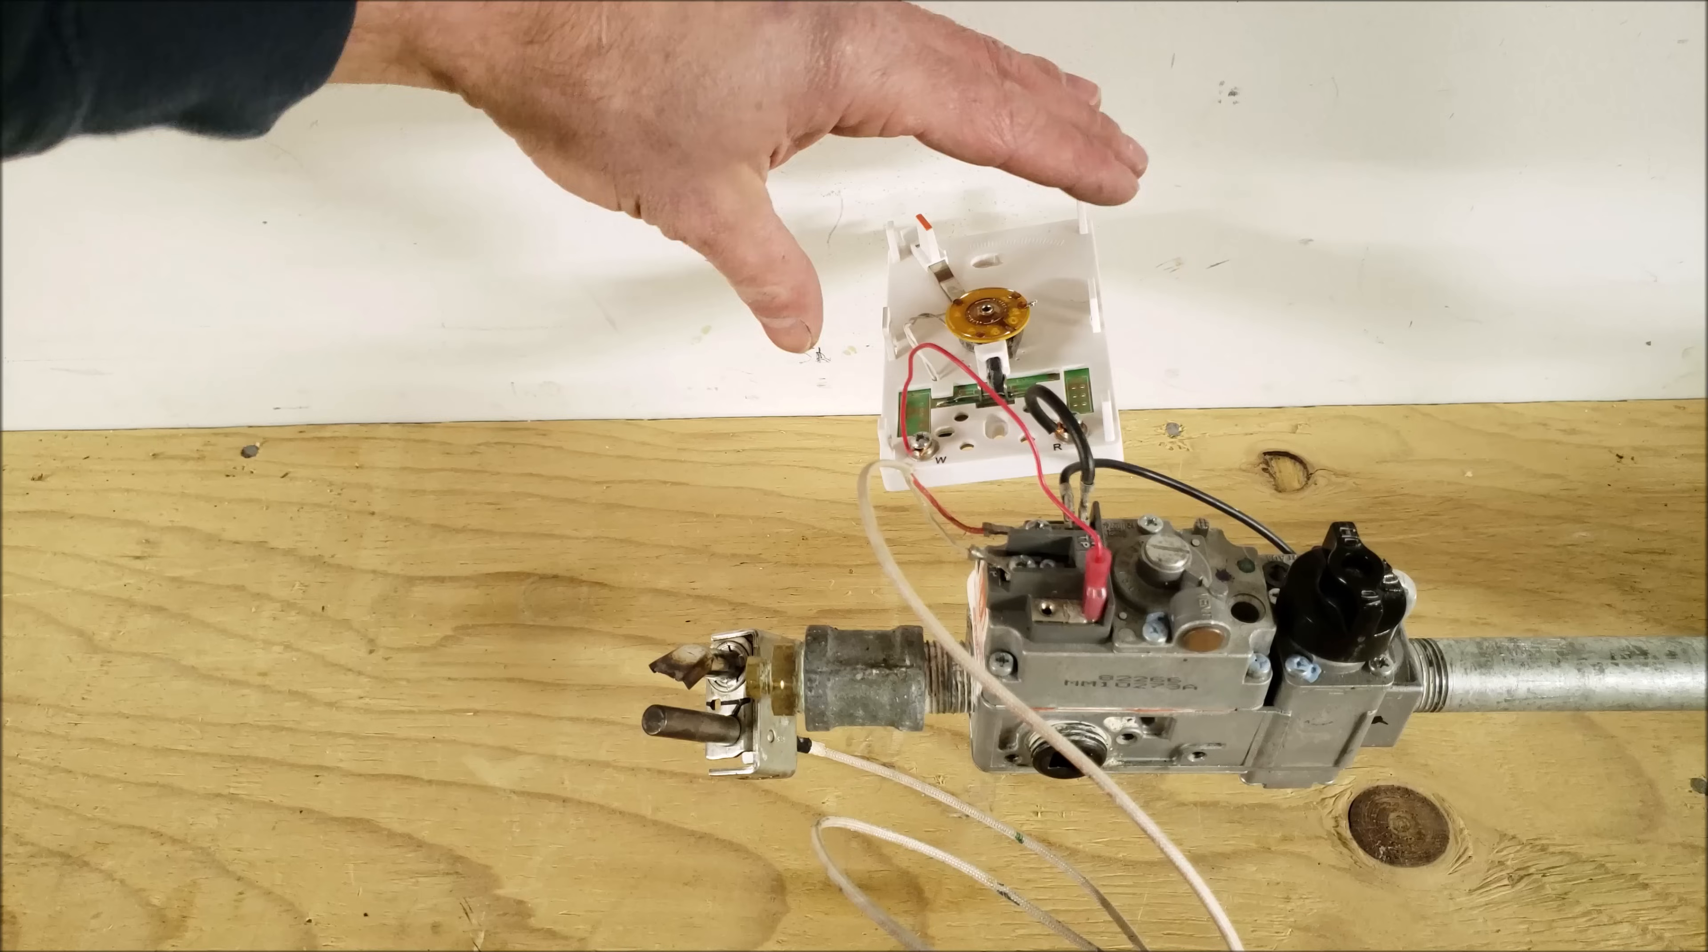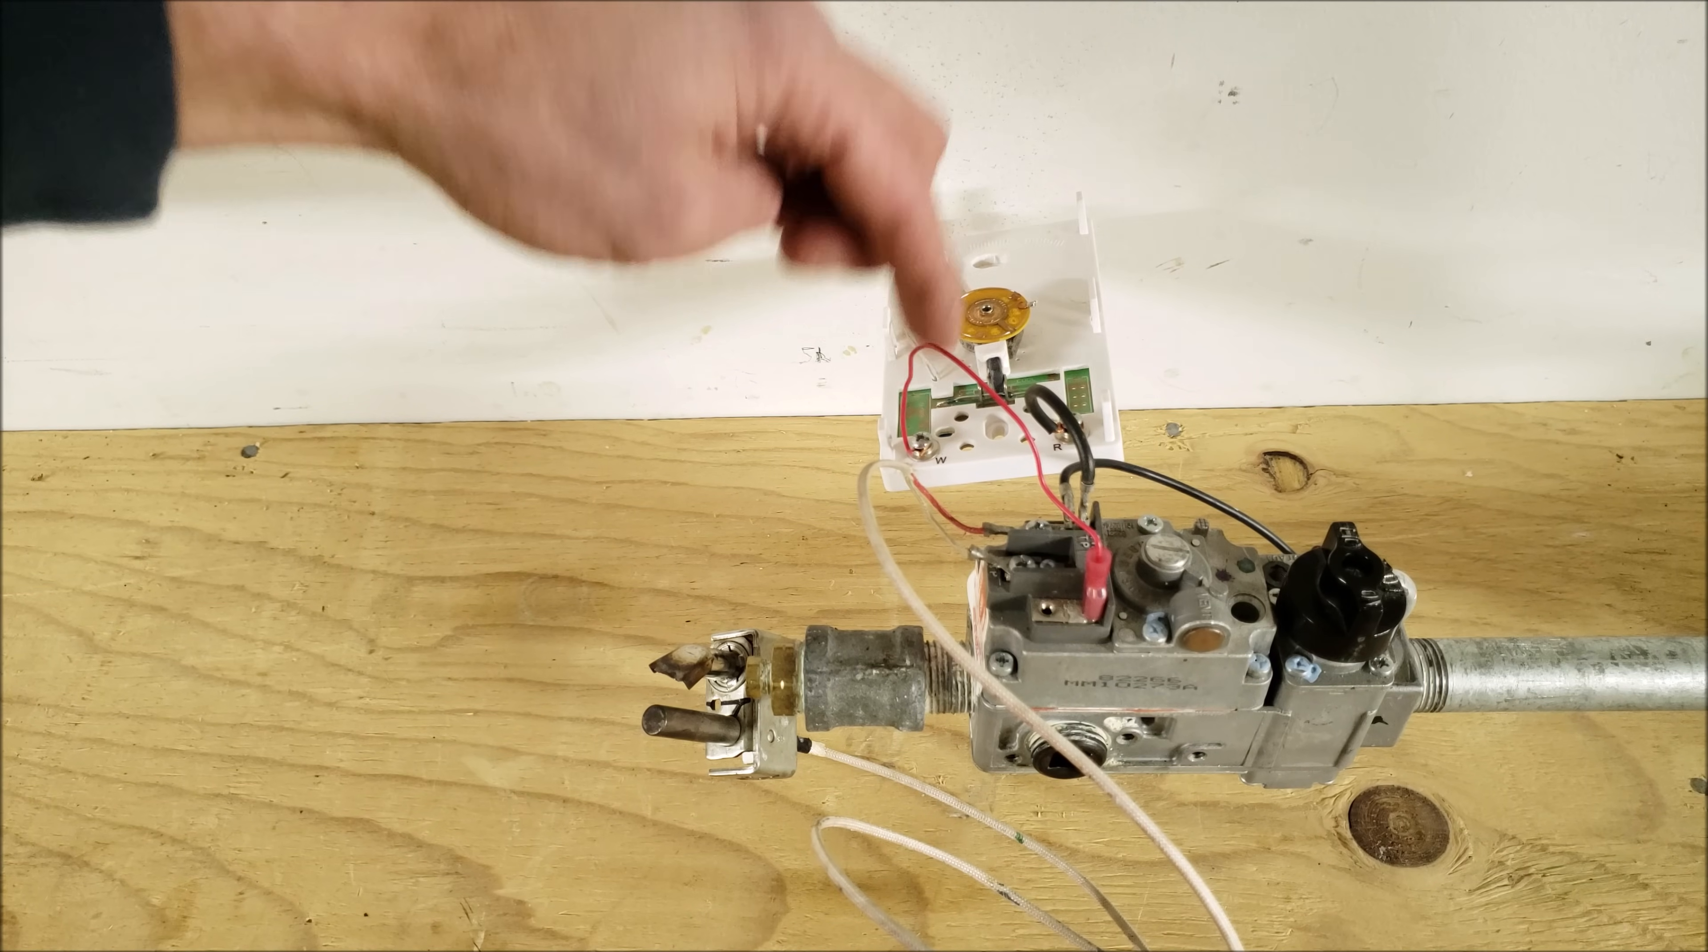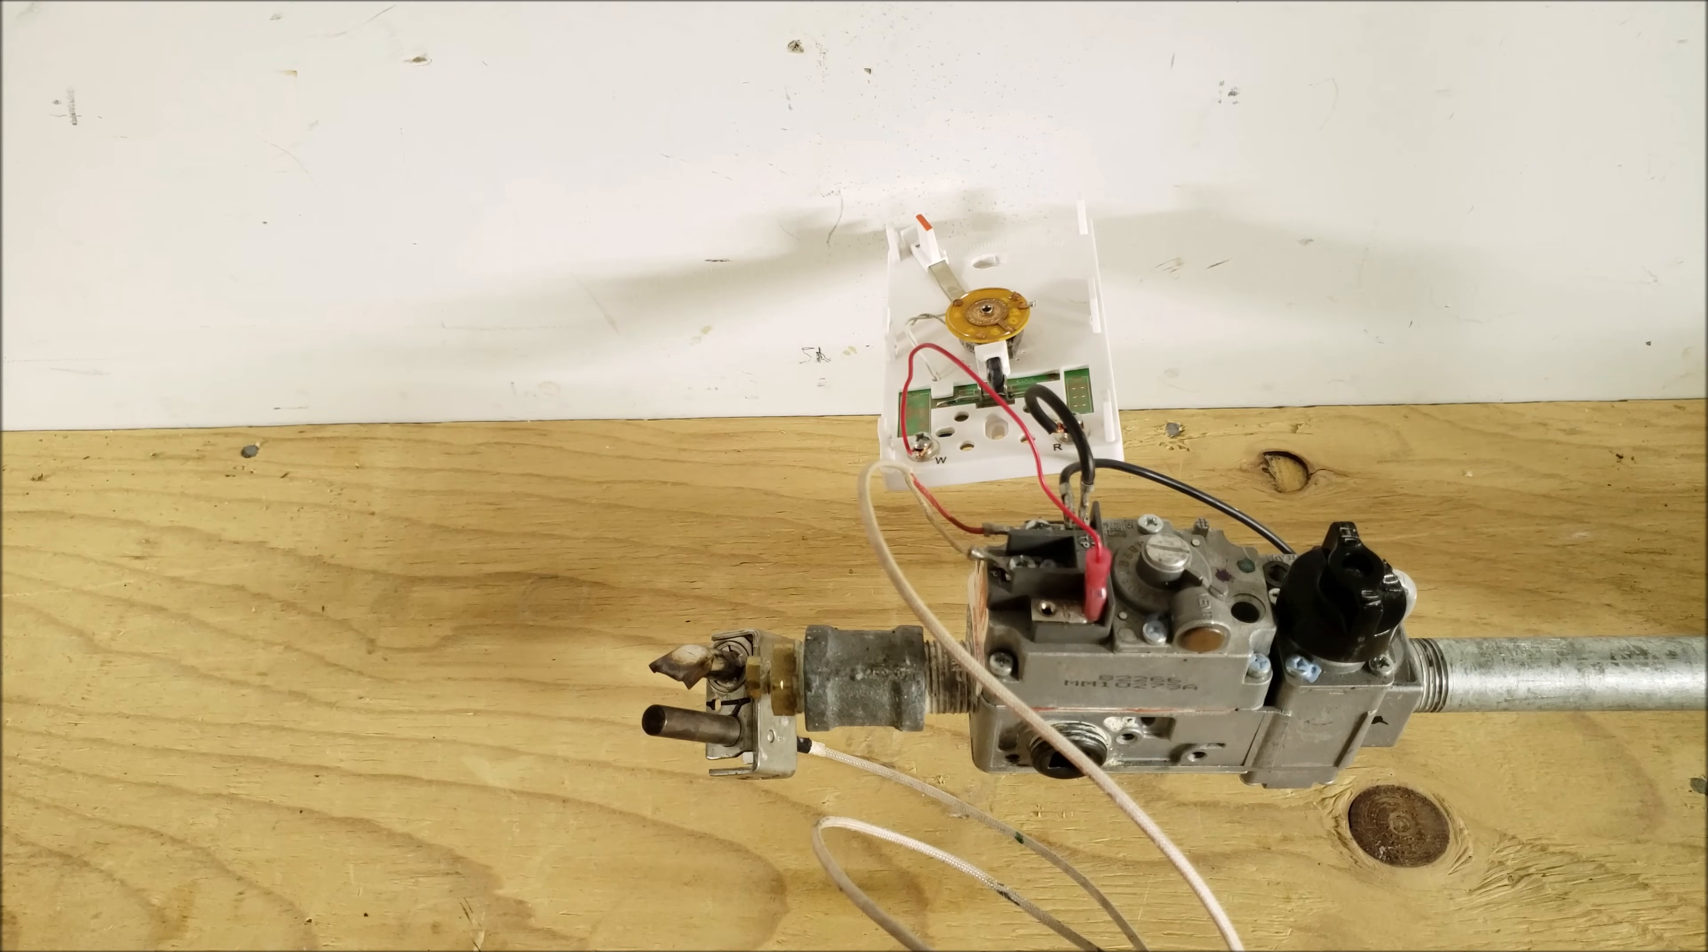So now we have our thermostat wired in for our main gas valve. We have our THTP connected to our R and this thermostat is normally open and then we have our W connected over to the TH. On a call for heat this will close allowing our millivolt power over to our TH in order to power the main gas valve.